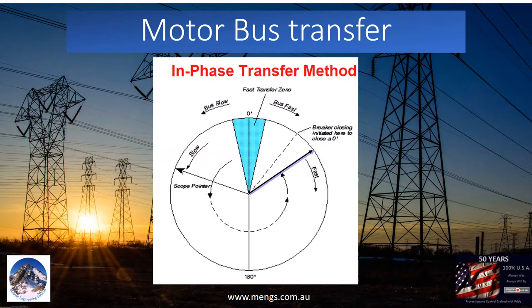After about 10 cycles of disconnection, the difference between the motor bus and the new source frequency is no longer constant or negligible. This difference generates a variable phase angle difference. The slip between the two sources is increasing, making the rate of change of angle difference faster. In such conditions, the time difference between sending a close command and actual circuit breaker closing becomes crucial, as the phase angle changes within this time. To compensate for circuit breaker closing time, the close command must be sent in advance so the breaker closes at 0 degrees. In-phase transfer is the scheme to facilitate this type of closing.